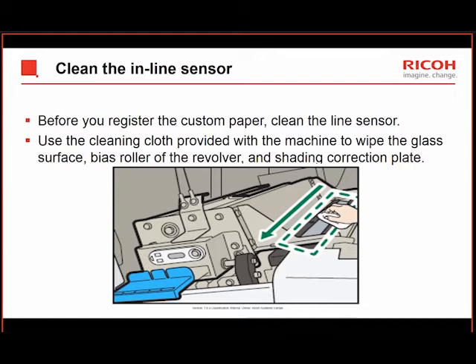There are 4 rollers on that sensor. So clean the glass first, then open it up, clean the roller. There are 2 white and 2 black rollers. The white rollers it uses for dark media, and the dark rollers it uses for pale or white media. So make sure you clean all of them. Again, the rollers in one direction only, and you just use a dry cloth for that.